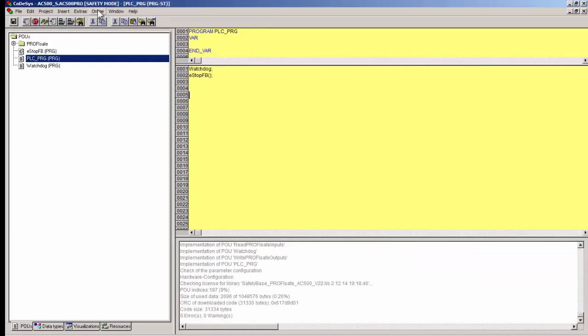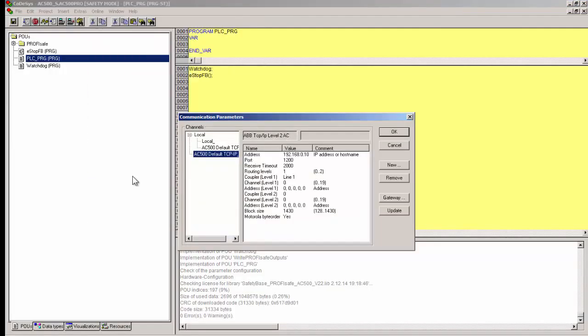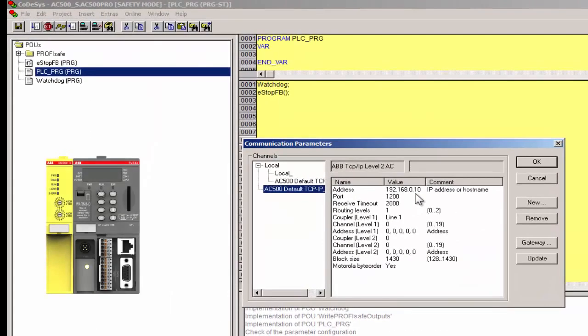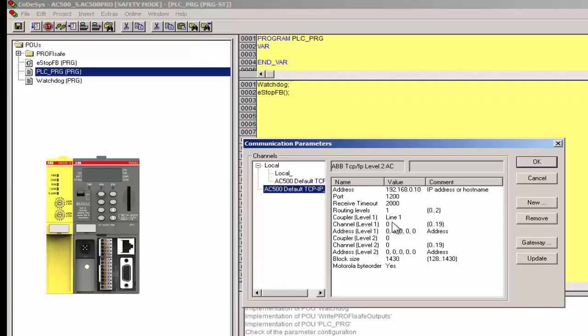The safety project is downloaded only through the non-safety CPU. Therefore, the non-safety CPU's IP address has to be set in this communication parameter setting. Routing level 1 denotes the project is routed from non-safety CPU to safety CPU. Line 1 indicates the coupler position of the safety CPU, in this example it is in slot 1.